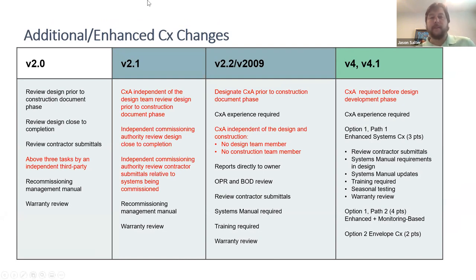One of the big changes that has occurred over time is when this commissioning agent or commissioning authority is involved in the process. As you can see, starting in version 2, the commissioning authority only needed to be involved prior to the construction document phase. However, as we move across all the way to version 4, you can see that it's now before the design development phase. So that's quite a bit earlier in the process. And it's so that the commissioning authority can check to make sure that the OPR and BOD are being carried through throughout the design and construction documents.